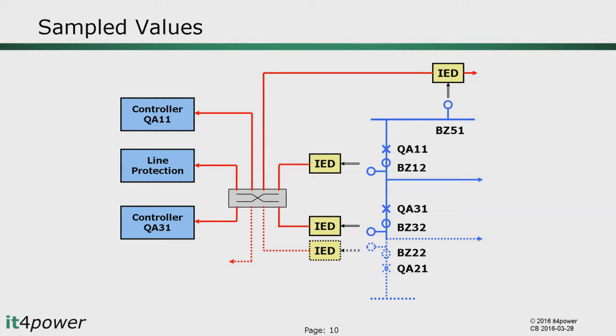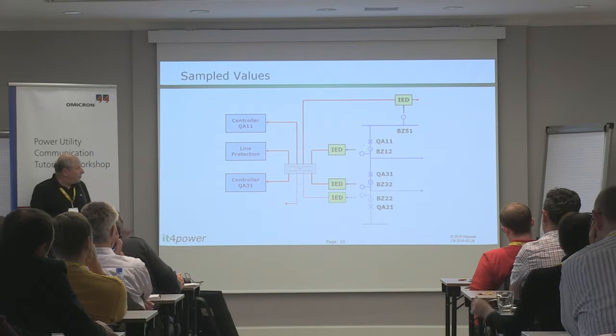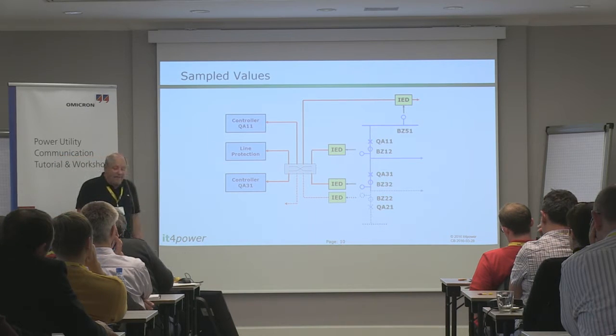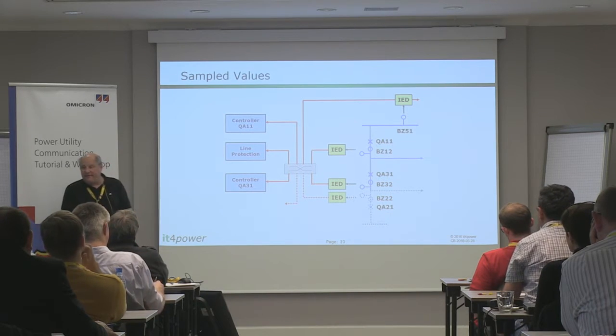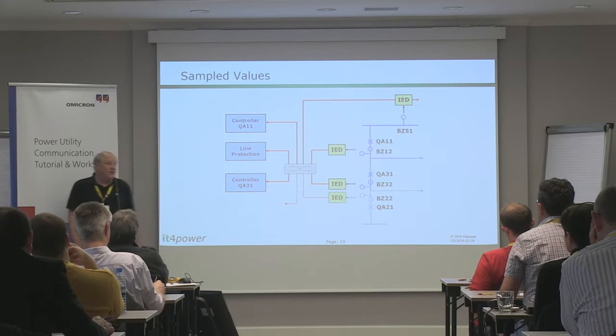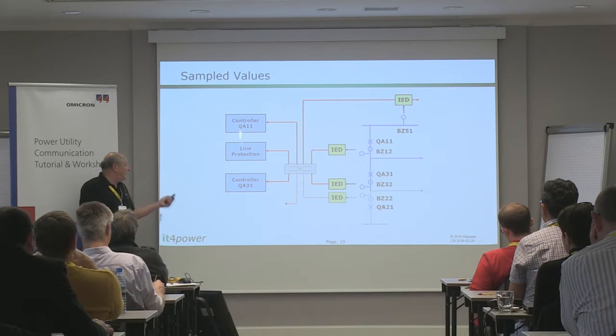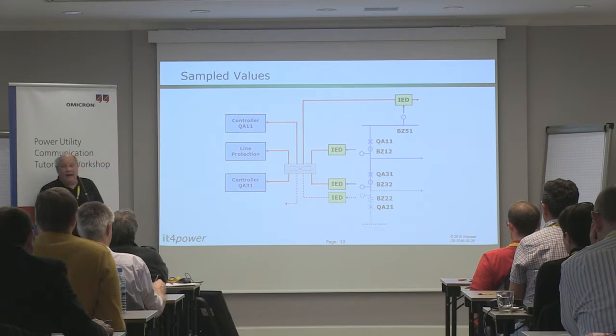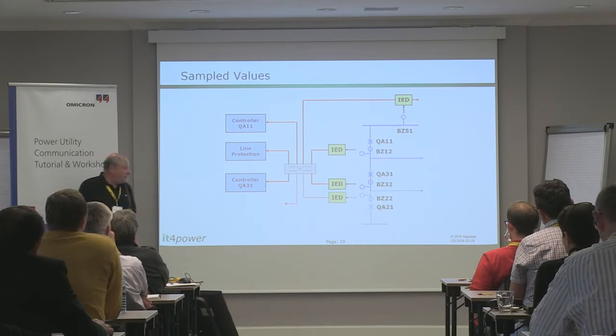Sampled values are used instead of performing analog-to-digital conversion inside the protection device. The conversion now happens down in the process where the current and voltage transformers are located, typically in what we call a merging unit. The analog signal is converted to a digital signal and a stream of samples is communicated over the network. Whoever needs that information can subscribe to it, receive it, and build their algorithms on the basis of those sampled value messages.